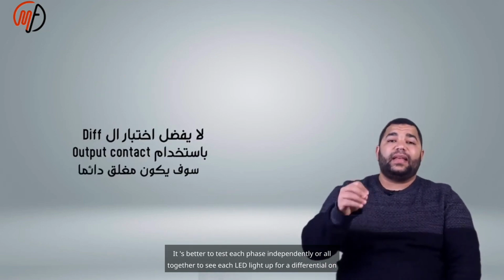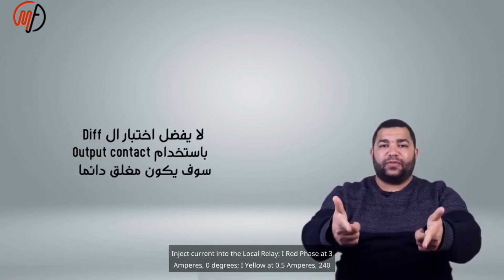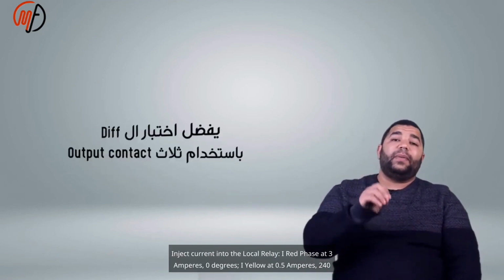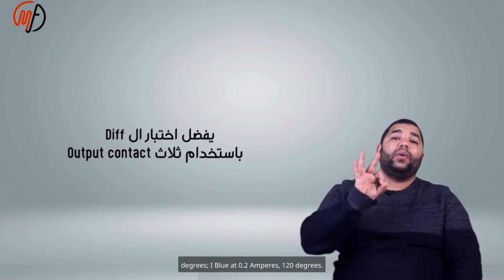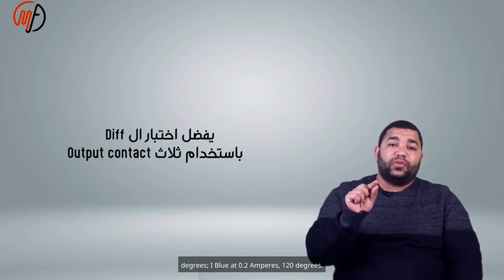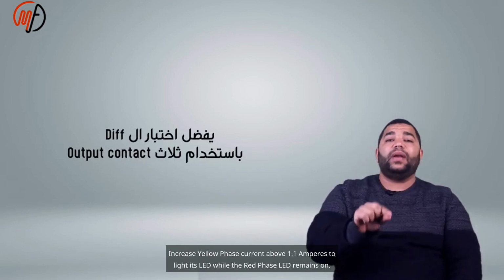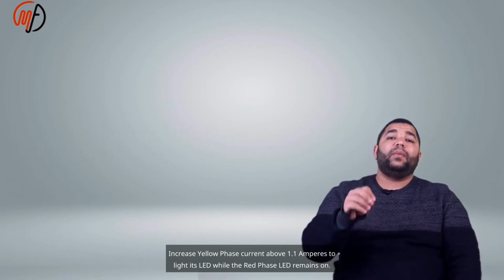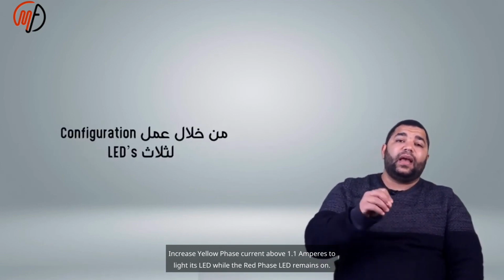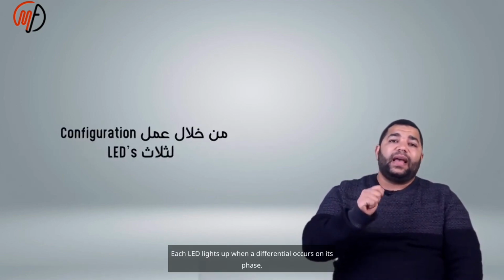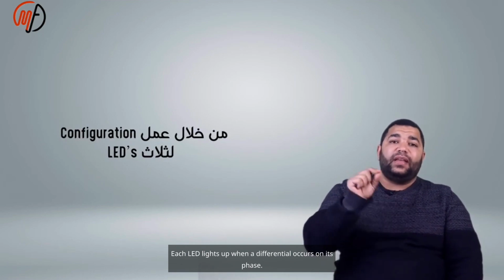differential on each phase. Inject current into the local relay: I red phase at 3 amperes, 0 degrees; I yellow at 0.5 amperes, 240 degrees; I blue at 0.2 amperes, 120 degrees. The red phase LED will light up. Increase the yellow phase current above 1.1 amperes to light its LED, while the red phase LED remains on. Each LED lights up when a differential occurs on its phase.